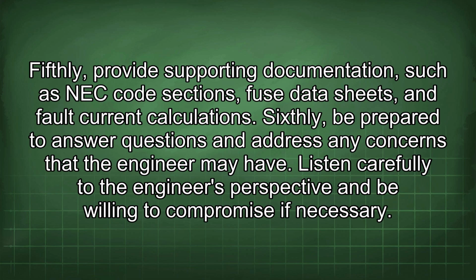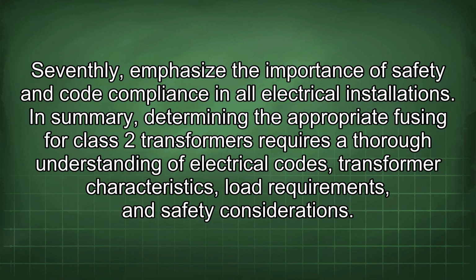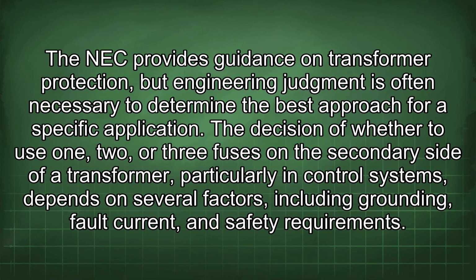Fifthly, provide supporting documentation such as NEC code sections, fuse data sheets, and fault current calculations. Sixthly, be prepared to answer questions and address any concerns that the engineer may have. Listen carefully to the engineer's perspective and be willing to compromise if necessary. Seventhly, emphasize the importance of safety and code compliance in all electrical installations. In summary, determining the appropriate fusing for Class 2 transformers requires a thorough understanding of electrical codes, transformer characteristics, load requirements, and safety considerations. The NEC provides guidance on transformer protection, but engineering judgment is often necessary to determine the best approach for a specific application.